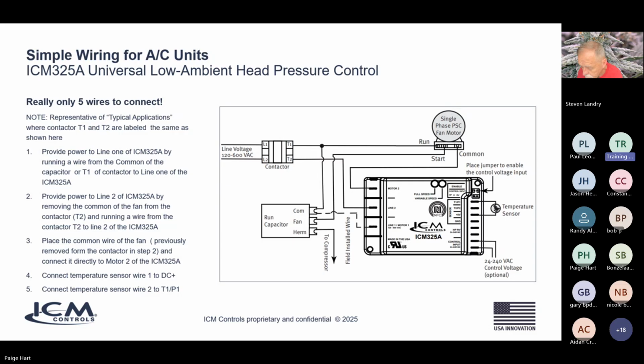Now, line 1, the dashed line, represents a field installed wire that goes to the common of the capacitor. So we're just picking up T1 power from the contactor. T1 is just the load side of the contactor opposite of line 1. When the contactor pulls in, that T1 power powers the common of the capacitor, and also powers line 1 of our control. T2 normally would have gone back to the common of the motor. It would have just gone to the other side of the motor. However, we're going to take that black wire off the contactor, not off the motor, and we're going to bring that wire to line 2 of the ICM. So now you've got a direct connection from the other side of the line to line 2 of the ICM. That's your 240 volts.